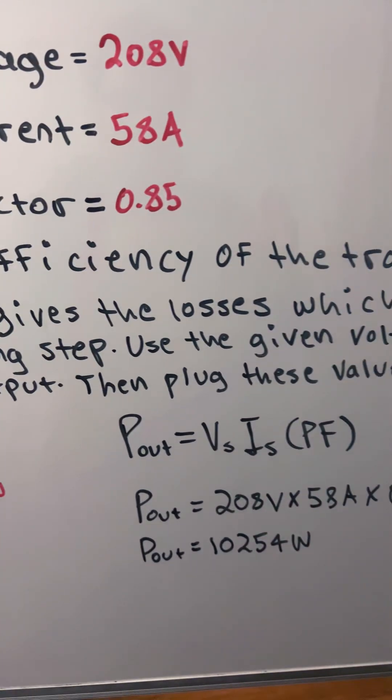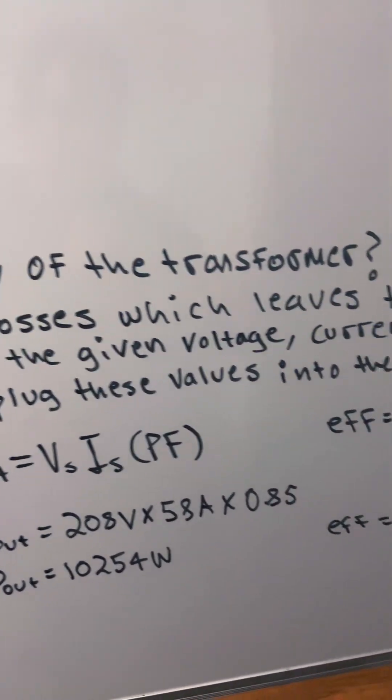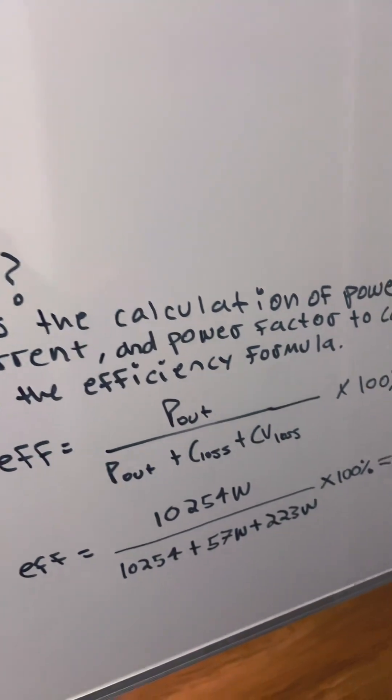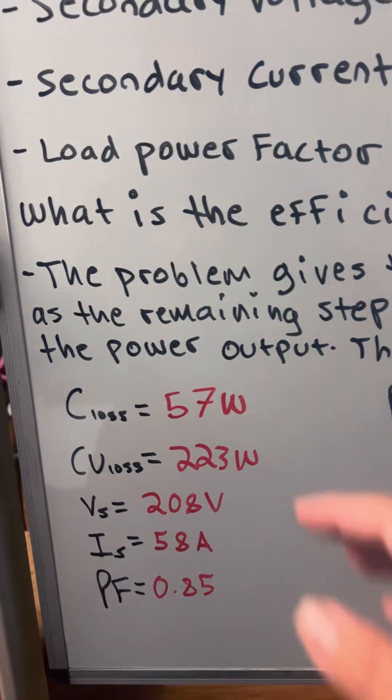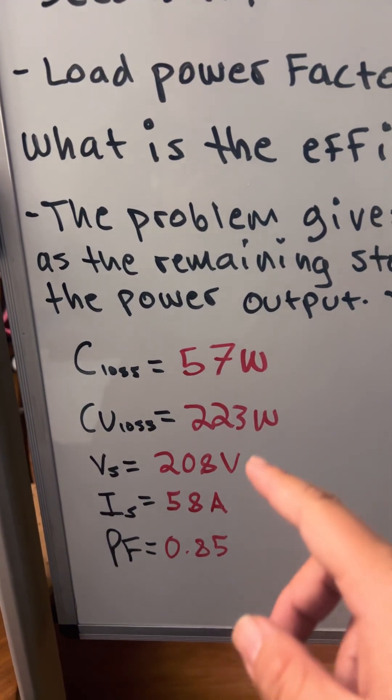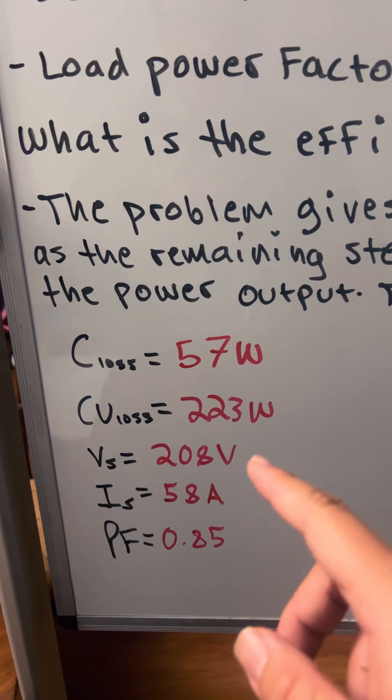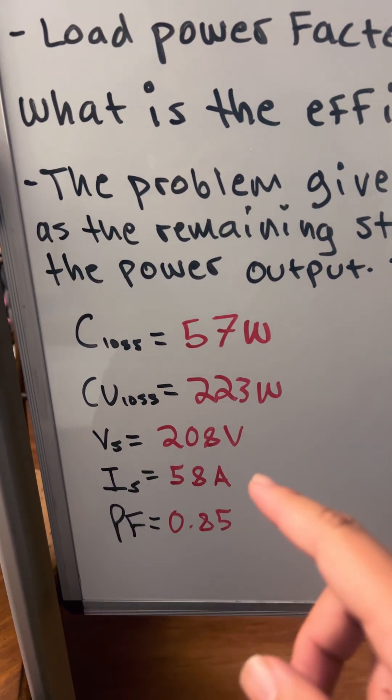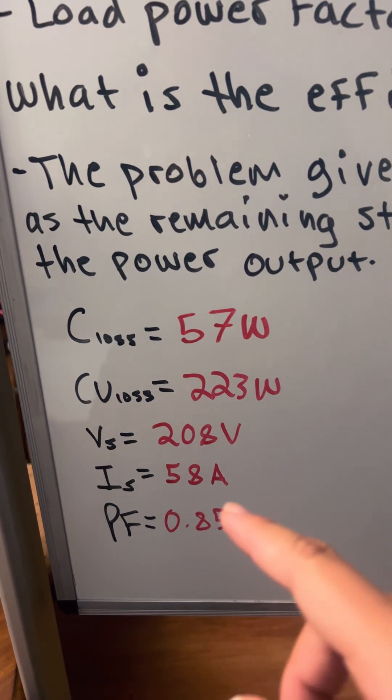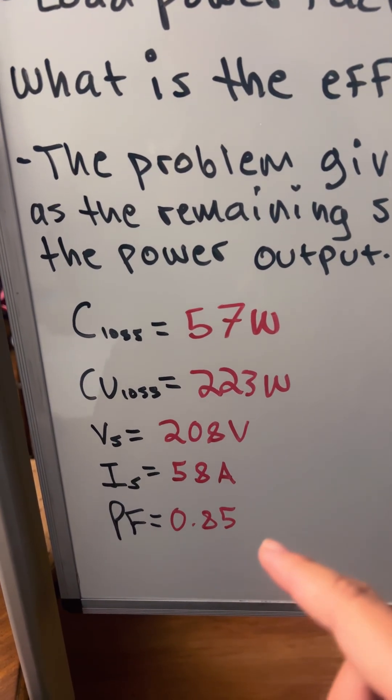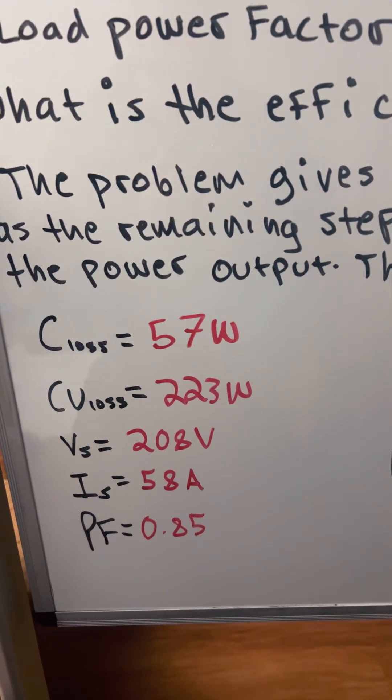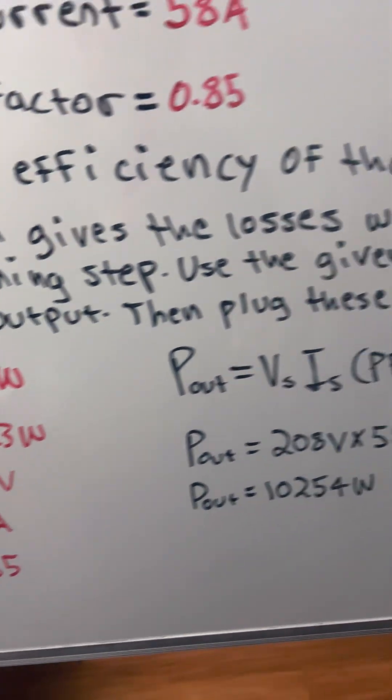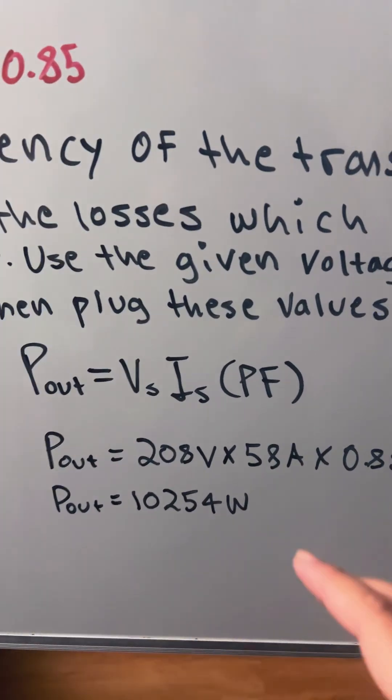Then we're going to plug these values into the efficiency formula. So we have core losses = 57W, copper losses = 223W, secondary voltage = 208V, secondary current = 58A, and power factor = 0.85. We're going to use the power formula first.